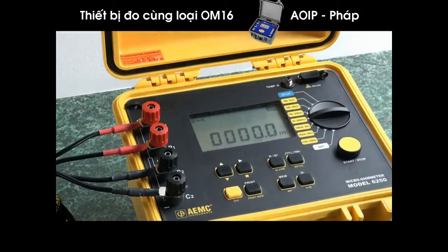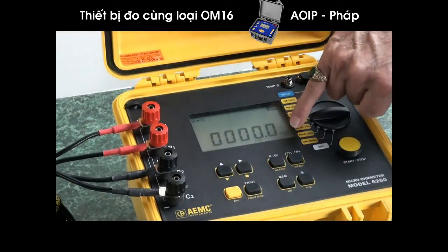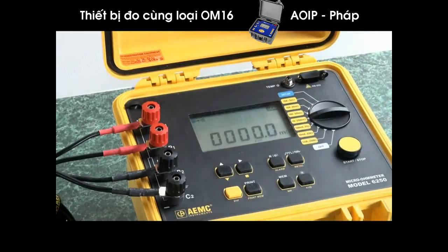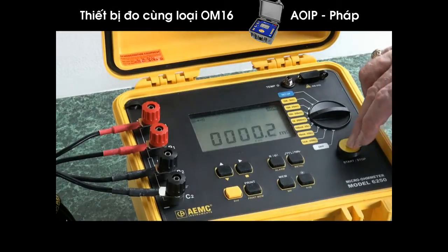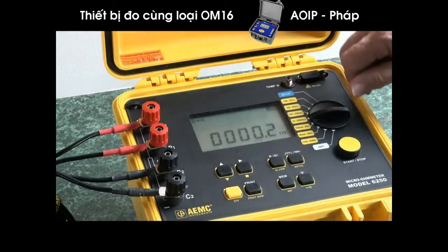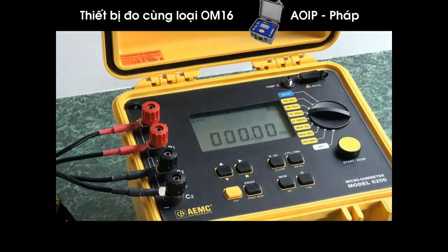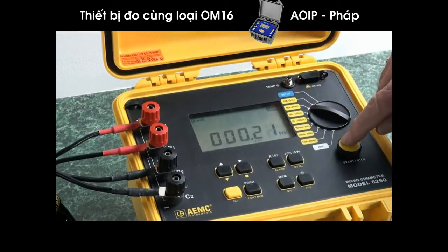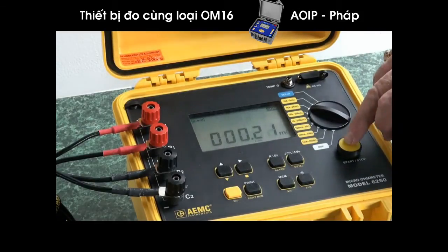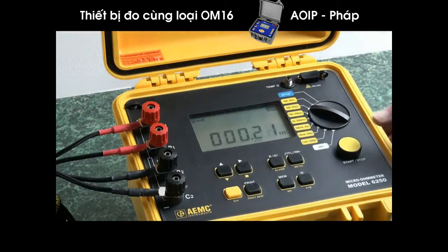We'll pump more current through it, and it just automatically changed into the milli-ohm region. Now we're reading two-tenths of a milli-ohm. We'll crank it up some more — running 10 amps through it. The decimal shifts two places and we find it's actually 0.21 milli-ohms. We still have further sensitivity to test, and we can run it at the 25 milli-ohm scale at 10 amps, increasing sensitivity by a magnitude of 10.